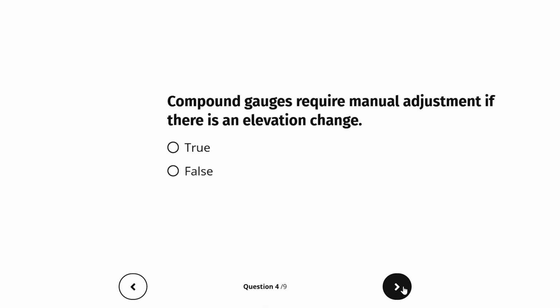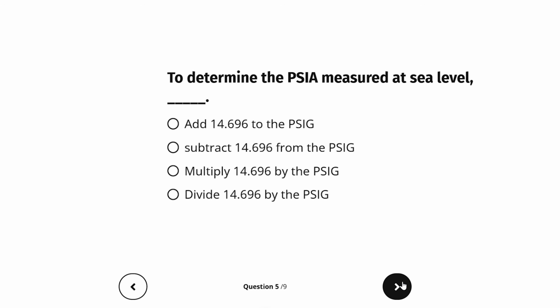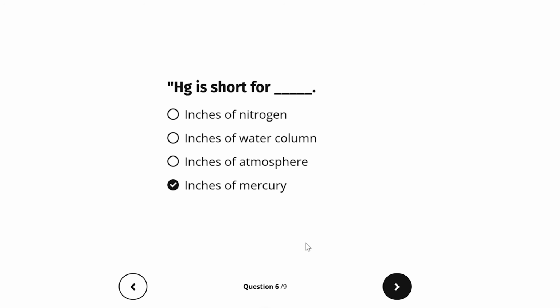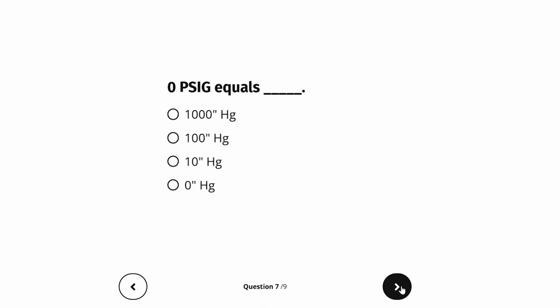30-inch Hg. Compound gauges require manual adjustment if there's an elevation change. And that's true because there's that adjustment screw towards the bottom of the compound gauge face. To determine the PSIA measured at sea level, do this: add the 14.696 to the PSIG to get your total measurement. Inch Hg is short for blank, and that's inches of mercury. 0 psig equals blank, and that's 0-inch Hg. Remember that as you go into a vacuum, your inches of Hg number is going to increase.